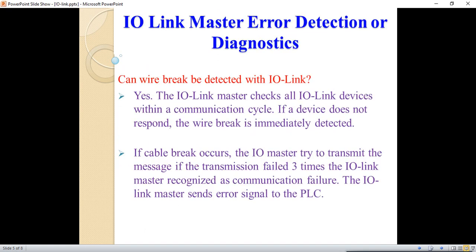IO-Link master error detection and diagnosis: another advantage of the IO-Link master is it can detect errors or faults. Wire breaks can be detected — the IO-Link master checks all IO-Link devices within the communication cycle. If a device doesn't respond, the wire break is immediately detected. If a cable breakage occurs, the IO-Link master tries to transmit the message; if it fails three times, the master recognizes it as a communication fault and sends an error signal to the PLC or controller.